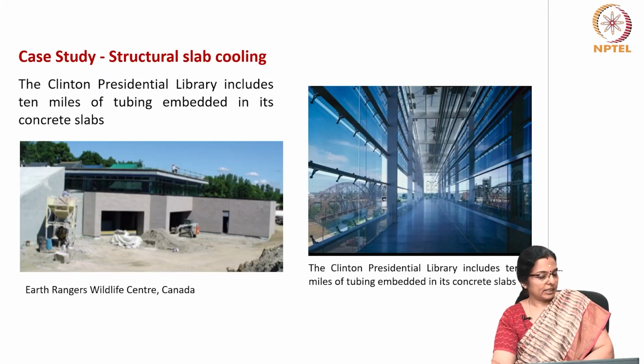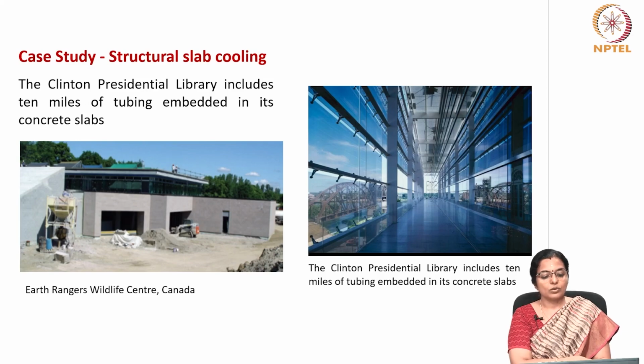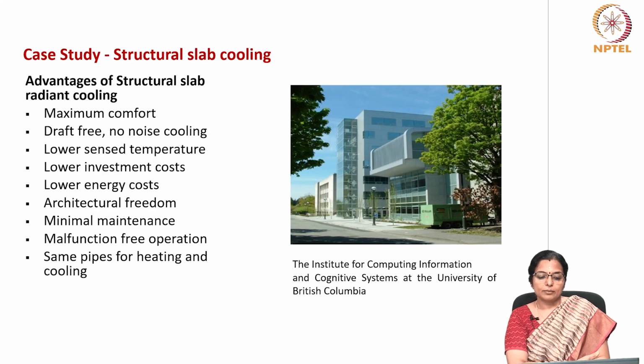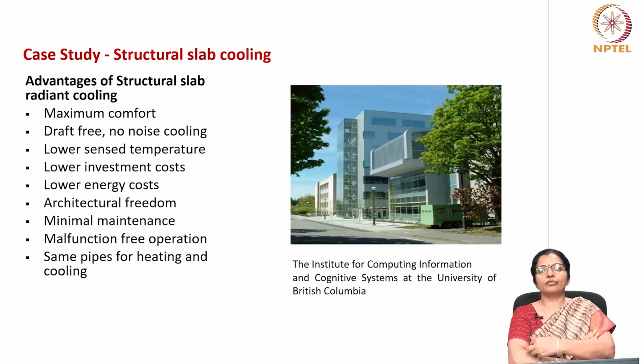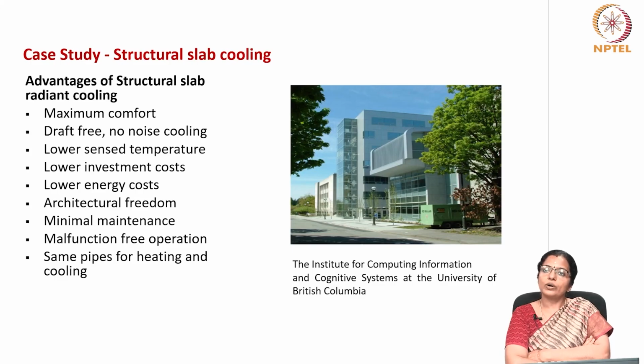Then another few cases where structural slab cooling is used is the Clinton Presidential Library, and it includes 10 miles of tubing embedded in its concrete slab. Now the advantages of structural slab cooling include that it provides maximum comfort, gives draft free or no noise cooling, has lower sensed temperature, has lower investment costs, has lower energy costs, gives the architectural freedom for design because it does not hamper the design of the building, requires minimal maintenance, and is malfunction free in its operation. The same pipe can be used for heating as well as cooling.